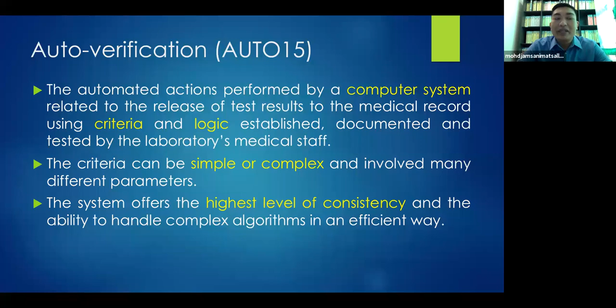Based on the CLSI guideline, auto-verification is an automated action that can be performed by the computer system based on criteria and logic that we establish. It can be very simple or complex, and it can involve many different parameters. But the most important thing is that this system can offer the highest level of consistency and the ability to handle complex algorithms in an efficient way. So this is the benefit that we want from auto-verification. Instead of a mental algorithm, auto-verification is a computer-based algorithm that can be either immediate verification of result, repeat analysis, reflex testing, addition of comment, or suggested manual step, including but not limited to the manual review of the result.